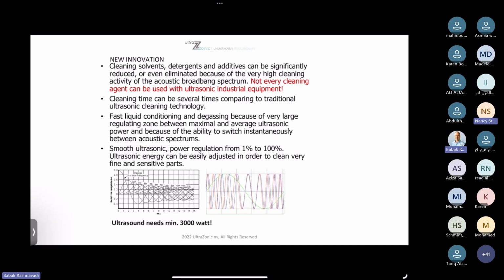That means you fill it up with water. In water, there is always some oxygen, and it has to be degassed for half an hour to be assured that there is no oxygen anymore in your water, because oxygen and cavitation don't like each other. They're really fighting each other. We cannot change it. So degassing first thing in the morning is one of the most important steps that you have to do.